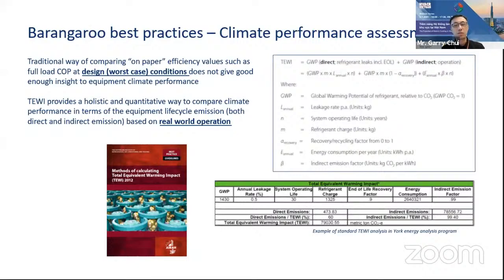by looking into the so-called COP, the coefficient of performance of the equipment, and in most cases it is at full load conditions, which represent the design or worst case conditions. However, looking at this on-paper efficiency value doesn't really give us good insight into the overall carbon performance of the equipment. For that, we have to look not at a single point of conditions, but at the overall energy consumption based on the location and the real-life operating conditions of the unit, what I call real world operations.